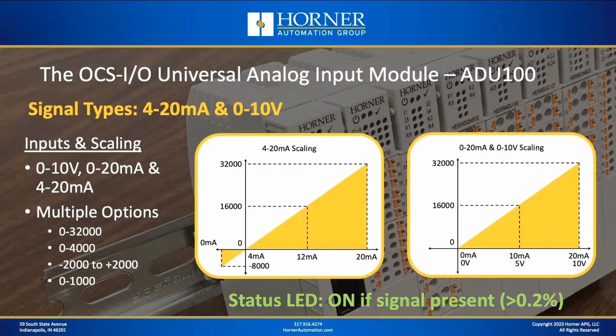Next, let's talk about the readings that come back. What format are they in? Well, remember, we're doing analog to digital conversion, so we're going to be getting a digital value back into our analog input register, and we have some choices as to how we want that data to come back. With the highest resolution, we can choose 0 to 32,000 counts. And if we just want real down and dirty readings that are easy to deal with, we can even do 0 to 1,000 as the range coming back. But we lose a lot of resolution in that case in exchange for what will probably end up being extremely stable signals. But all my charts here are assuming we choose the highest resolution available.